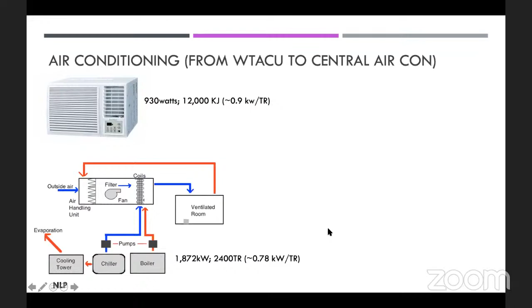Of course, that's then the AHU. That resulted in savings of about 1,700,000 kilowatt hours per year. So from window type going to centralized, that's the total demand and the savings on peak demand. We had a demand factor of 0.7 based on hospital operations, and considering hours in a year, the energy saved is about this much.